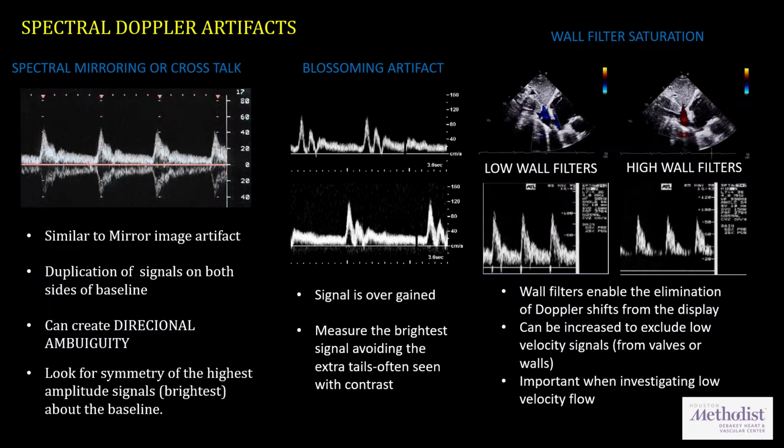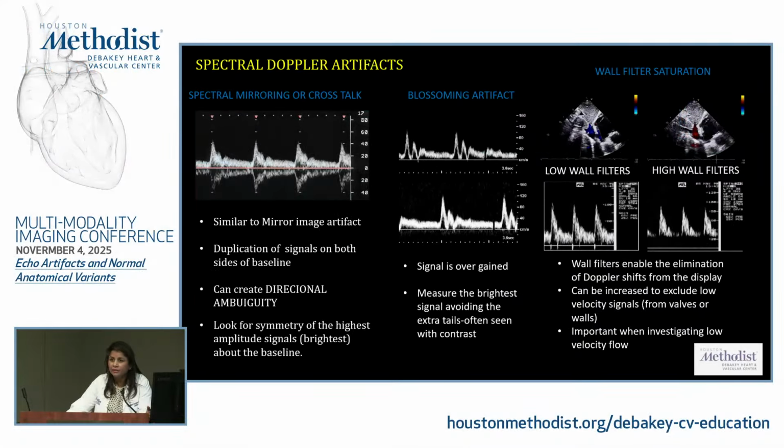How many of you know what a wall filter is, guys? Did you ever even think about wall filters? Actually, very important. Because what are wall filters? These are filters embedded into our ultrasound platforms to remove the low velocity signals in the background. Important when you're identifying or analyzing low velocity signals, like for example, hepatic veins, right? Important to know what your wall filter setting is before you analyze the Doppler data.